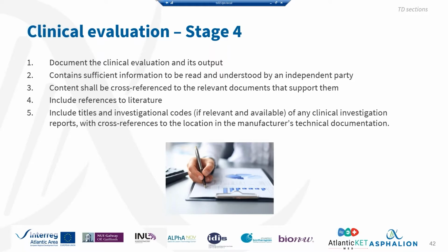That means usually here in the final stage of the clinical evaluation report, you have to weigh down the risks and the benefits. Obviously, your outcome should be positive. There should be more benefits than risks. However, you don't perform the risk analysis within the clinical evaluation report. You do it in another section of the technical document. So you have to make a reference from within the clinical evaluation report to show where you obtained the information regarding the risks.